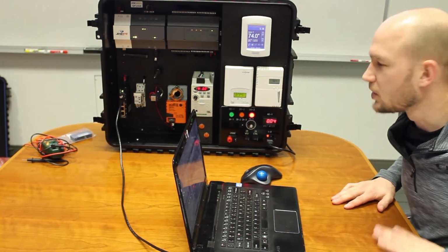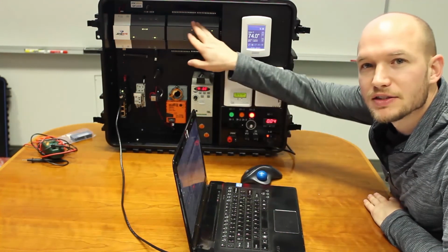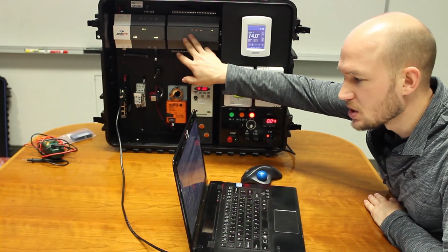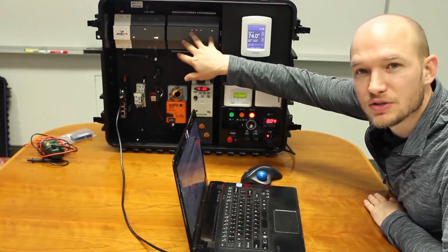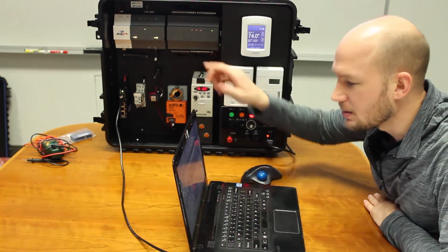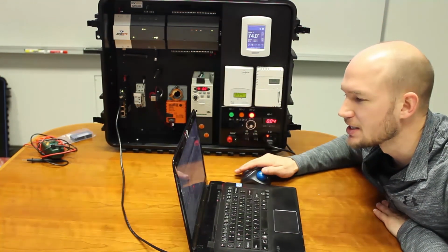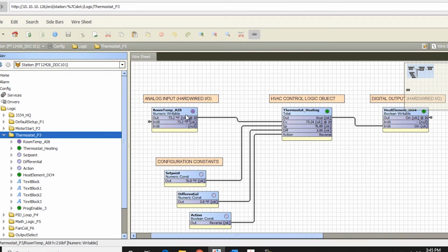To give you a quick overview, this is the IO34 module, where the HVAC logic resides. What inputs on the computer is this feeding to? Room temperature is analog input 8. The output, 73.2, is feeding into the logic, as you can see here, and that's feeding out to digital output - heat element, digital output 4.